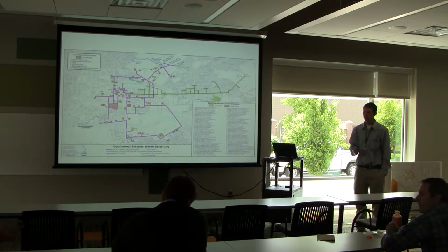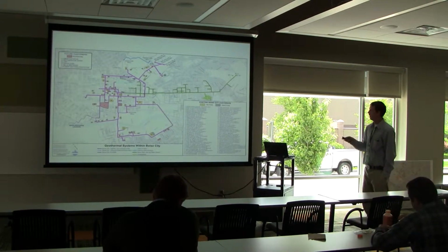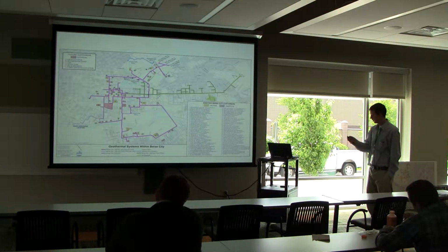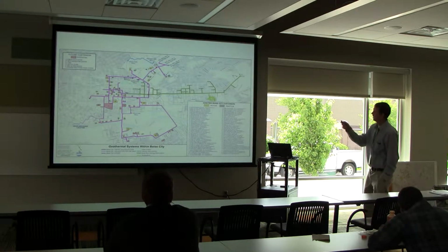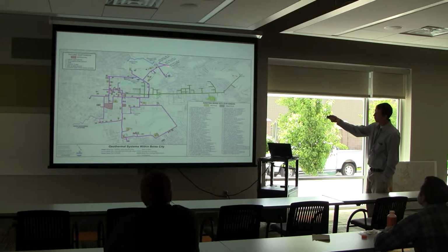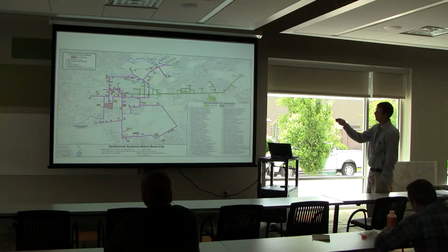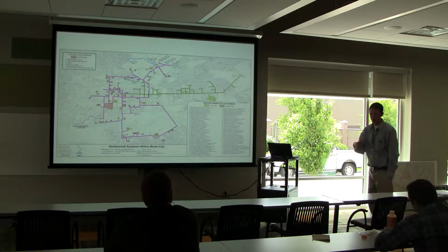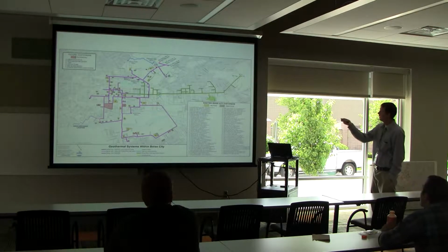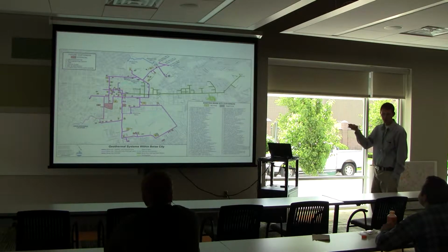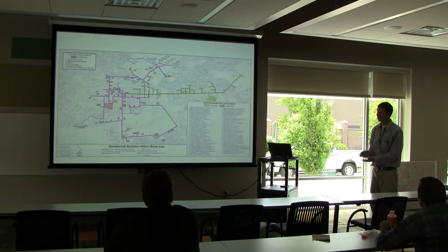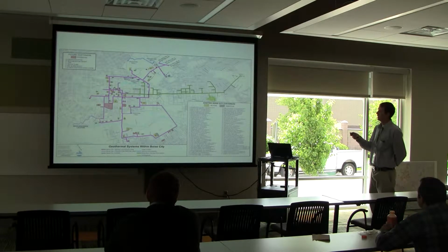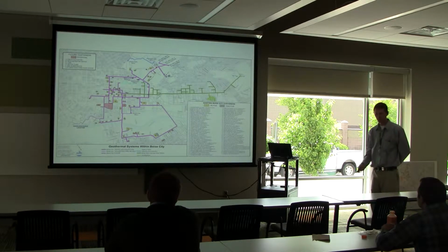John, are all 3 systems the same temperature coming out of the ground? More or less. All the wells—Boise Warm Springs' wells, our wells, and the VA wells—you can literally draw a straight line connecting them all, and that's not a coincidence. There's a fault line that runs right here, and water takes the path of least resistance. Historically, this is the line where Artesian Springs were coming out, so we can tap into the water. Our wells are about 400 to 600 feet deep. In contrast, our injection well is 3,600 feet deep. The aquifer is really 3,600 feet down; it's just that it follows this fault line.